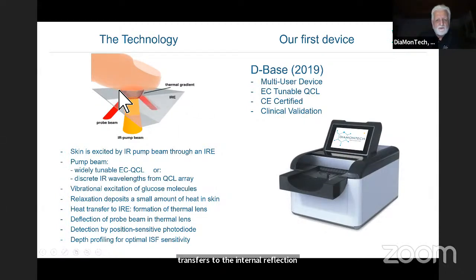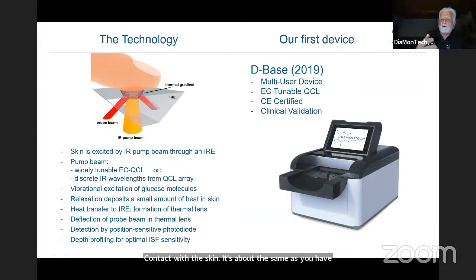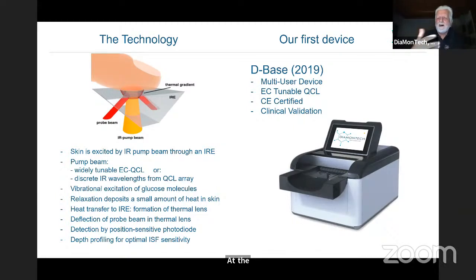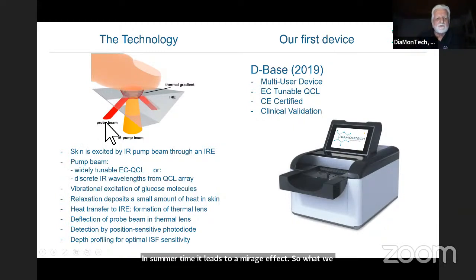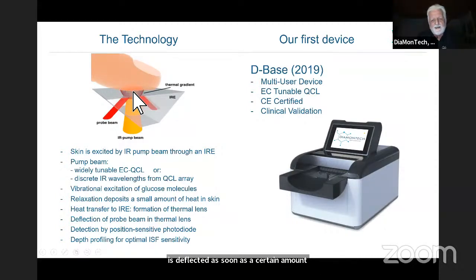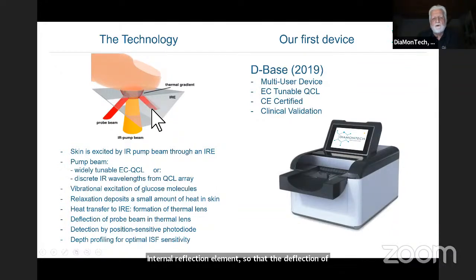And in this internal reflection element, it creates a temporary thermal lens because we use pulsed excitation. And this thermal lens in the IRE in contact with the skin is about the same as you have in the air on a hot asphalt street in summertime. It leads to a mirage effect. So what we do here, we use a second laser, which is a simple red probe beam laser, and send it through this thermal lens. And it is deflected as soon as a certain amount of heat from the skin layers enters this internal reflection element. So the deflection of the probe beam is a measure for the concentration of glucose. And we detect this deflection here with a simple position sensitive photodiode.